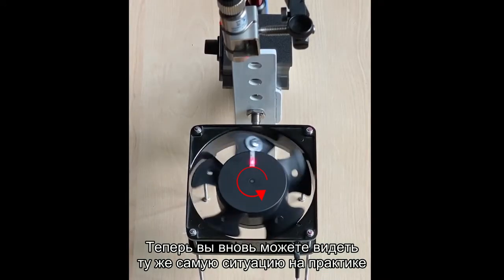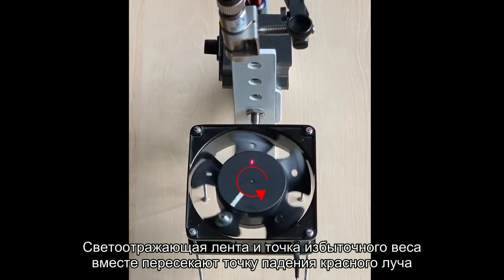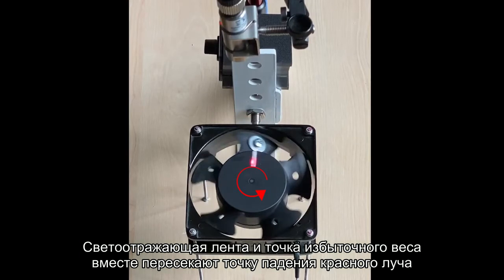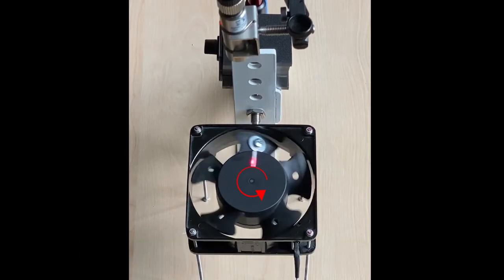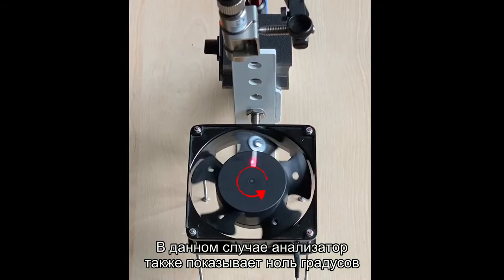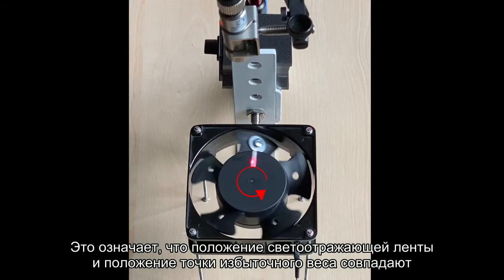Now you can see again the same situation in practice. The reflective tape and heavy spot go through the red ray point together. The difference is 0 degrees. The analyzer displays also 0 degrees in this case. It means that the reflective tape position and the heavy spot position are the same.